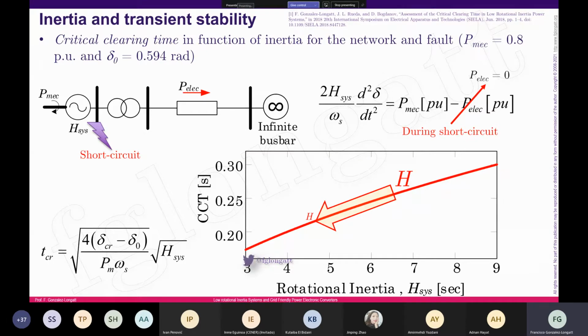But right now, the situation is going the other direction. If we reduce the rotational inertia so much, the critical clearing time starts to reduce. What's the main impact? We're losing the robustness of the electrical power system, but more importantly, we're creating a burden for overcurrent protection and other protection schemes, because they need to open and isolate the fault before we reach the point of instability.